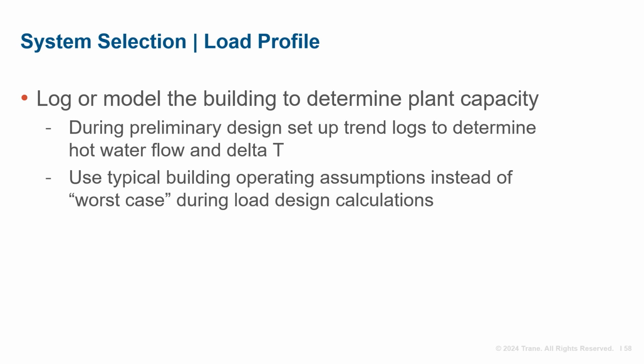In many cases, this results in more pieces of smaller equipment. Of particular interest are heat pump plants serving double duty. For example, in cooling dominant climates, equipment sized for cooling will cycle in heating mode. Another facet in these projects is to determine how low the fluid temperature can be reduced.